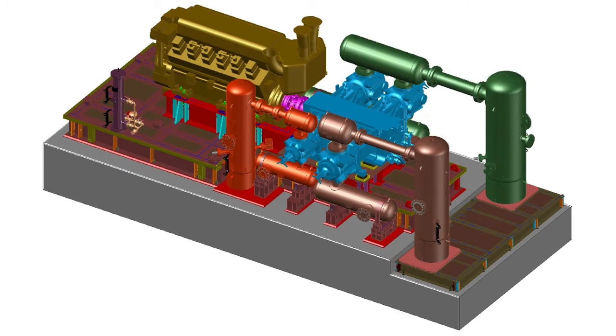Notice from this 3D package model, the scrubbers and process gas piping are structurally separated from the main equipment skid. Separating the mechanical and acoustical energy sources significantly reduced vibration. We refer to this as our hybrid foundation concept.